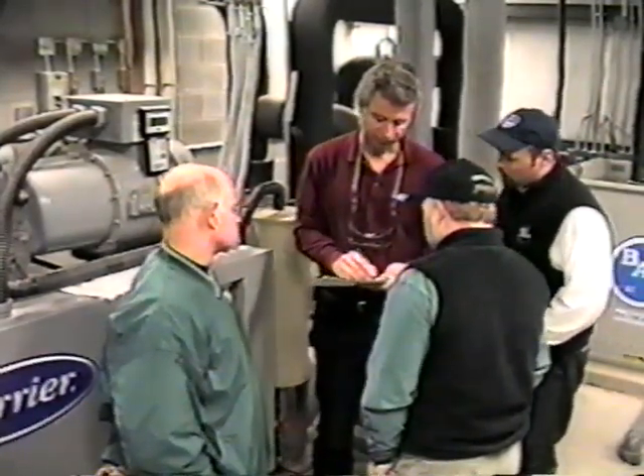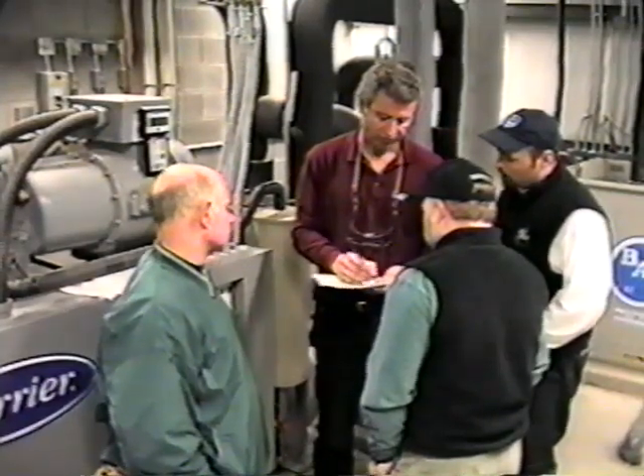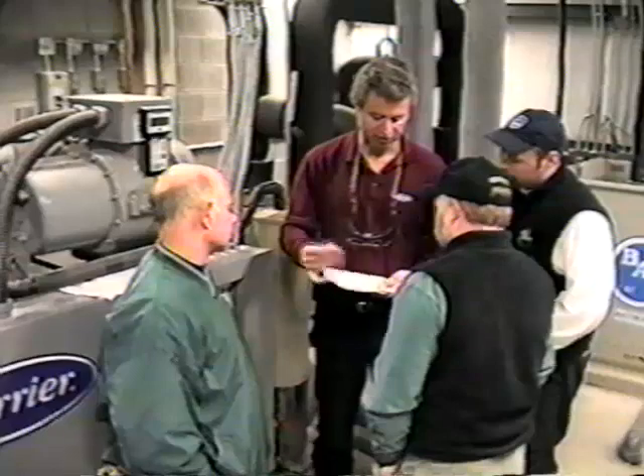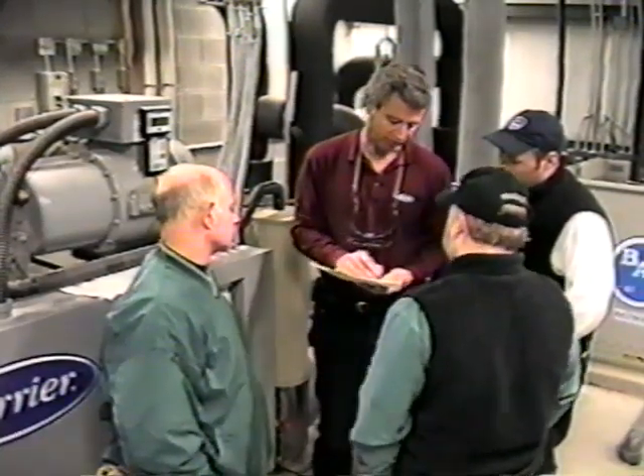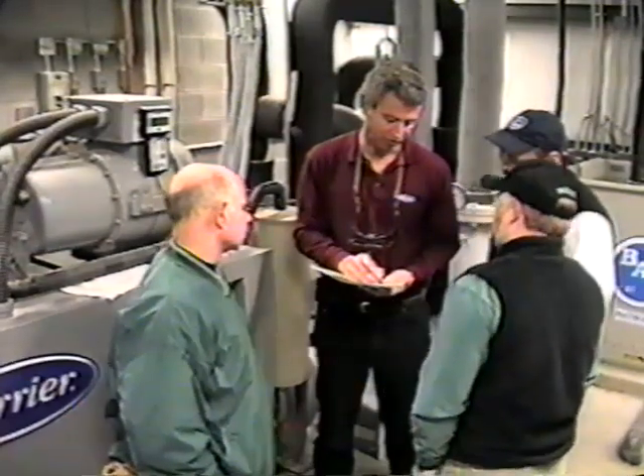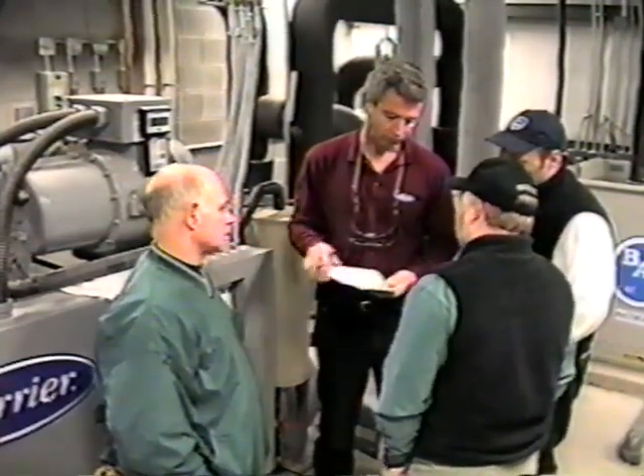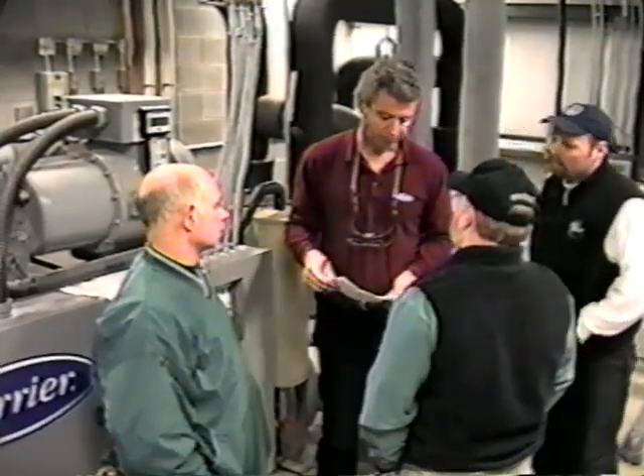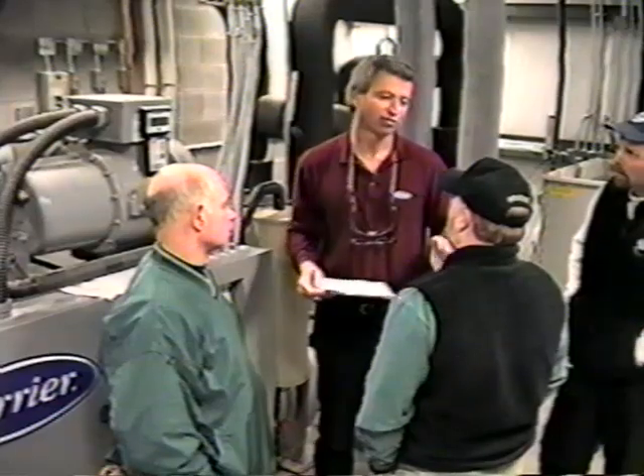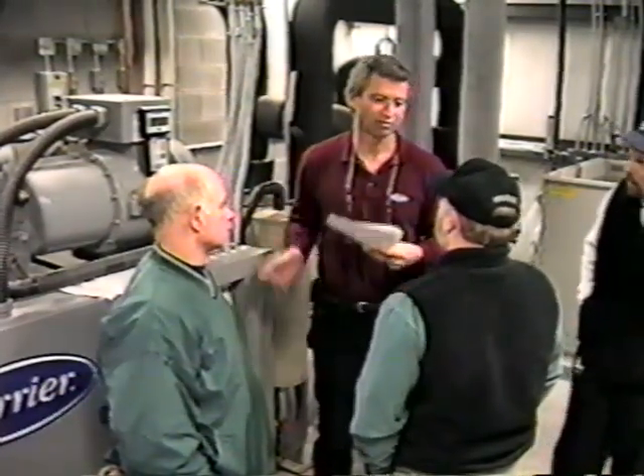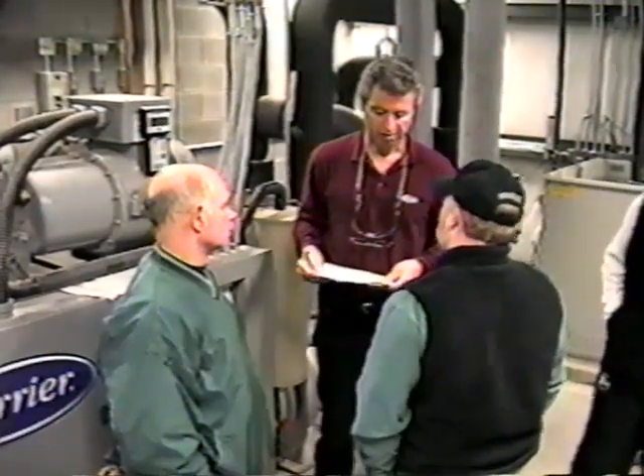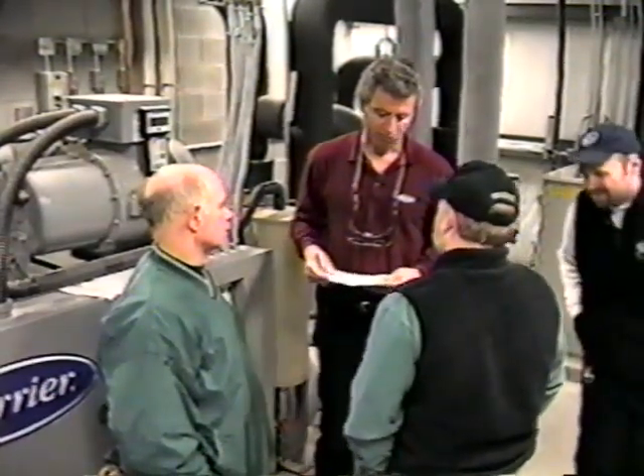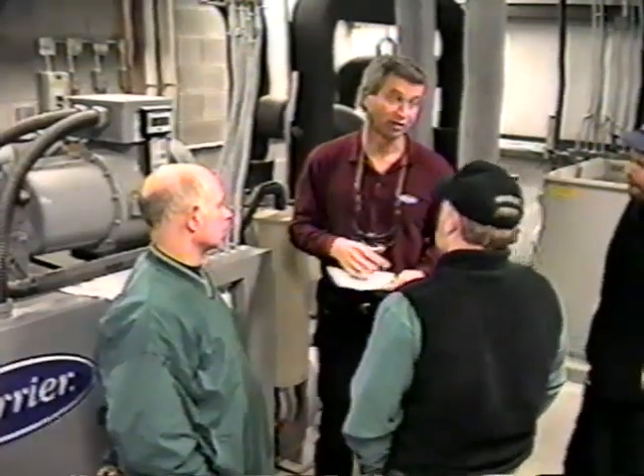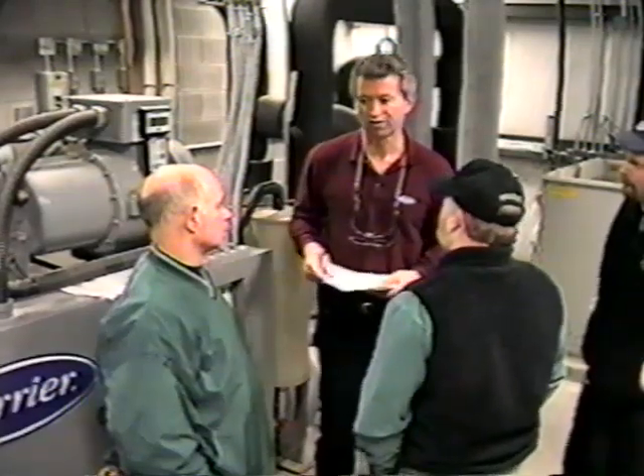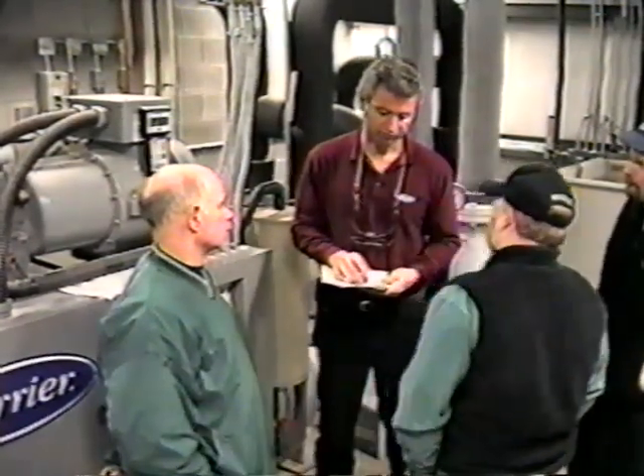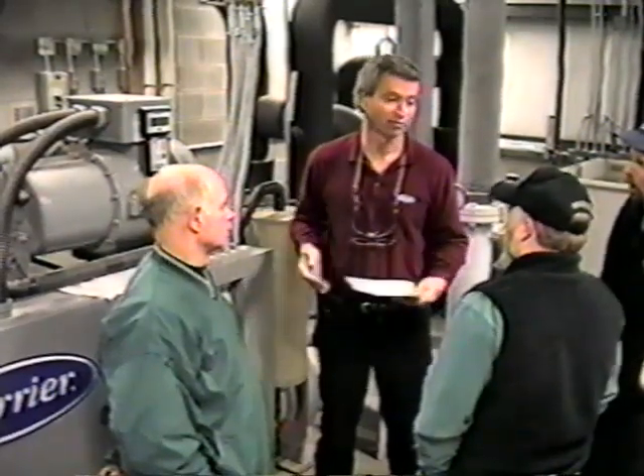Again, on the operating circuit, it wouldn't hurt to write those down. As long as you're taking these pressures, you might as well take the other 2 or 3. Anything with A2 isn't going to be there anyway. The manual tells us the hour meter is on the starter. Oil pressure is difficult because it's a function of your head pressure versus your suction pressure, so that varies the acceptable limit. Essentially, if you're in a condition that's not normal, the machine will tell you anyway. If your oil filter differential gets high, it will tell you it's time to change the filter.